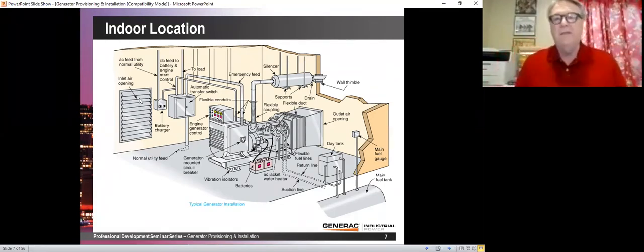So in that case, most inspectors, and you need to check with the inspector, would not require the fuel vents on the tank to go to the outside if it were a diesel generator. But if that is motorized louvers, then they definitely would. And of course, motorized louvers are nice because you can keep the building warm, because they keep the airflow from circulating through the building until the generator actually starts operating.